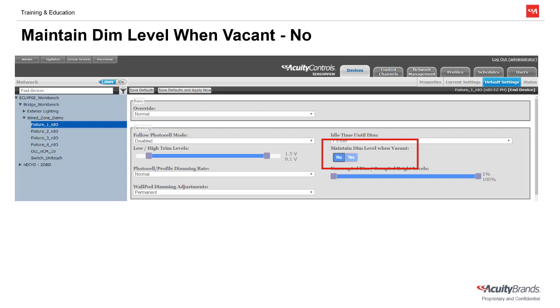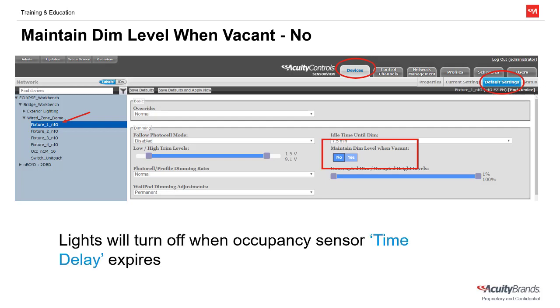Let's discuss where in Sensor View we can find the Maintain Dim Level When Vacant setting for the devices. You'll notice that we are in the Devices tab, and then the default settings of an output device — in this case an NLIGHT enabled fixture. The Maintain Dim Level When Vacant setting is set to NO out of the box from the factory, which means that the lights will turn off when the occupancy sensor's time delay expires.